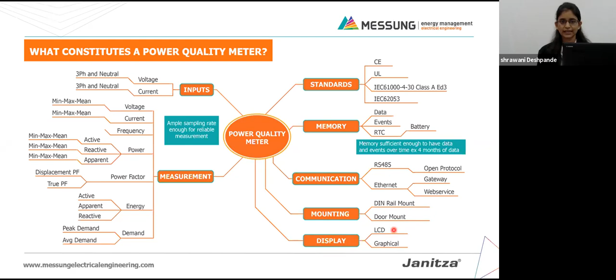Now let's see what a class A power quality analyzer is, or what we mean by class A. So class A is a legally verifiable standard. This class A is used where precise measurements are necessary, for example, for contractual applications, or for resolving disputes between utility companies, or for complying to various standards. Now, as you can see, IEC 61000-4-30 has defined certain measurement methodologies for various power quality parameters. For each parameter, such as flicker, harmonics, voltage, for every parameter, they have defined certain limits and certain measurement methodologies.